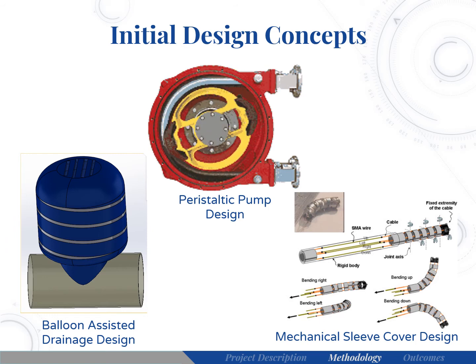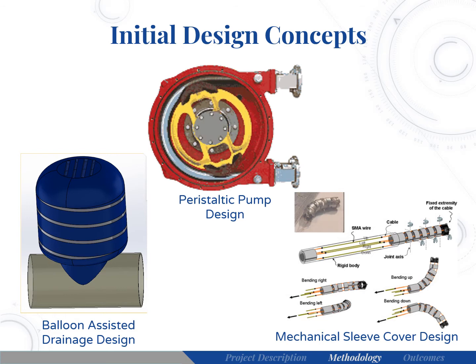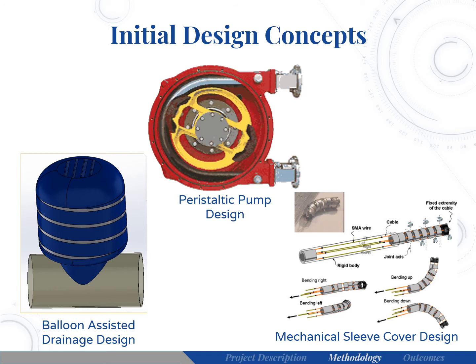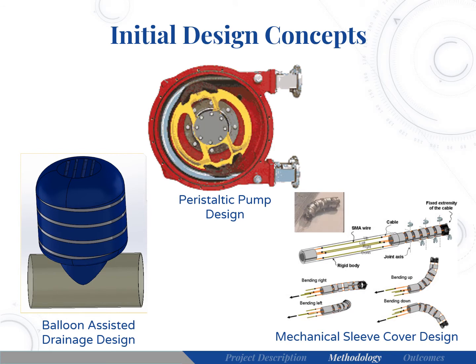Our second design is based on a peristaltic pump, as shown in the middle of the screen. Essentially, the pump would be held within a small device which clamps onto the catheter line. The device would have a sensor, potentially based on pressure, which would sense if there is stagnant urine in the line and trigger the pump to turn on. However, a major downfall of this device is that it would be very difficult to cause it to fail with the catheter line open, so that the urine would still drain with gravity if our device fails.